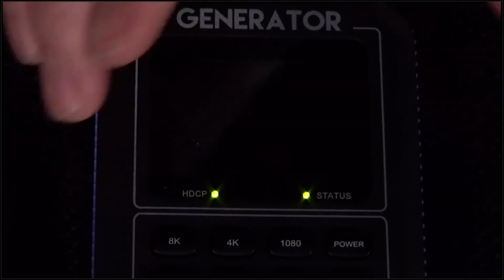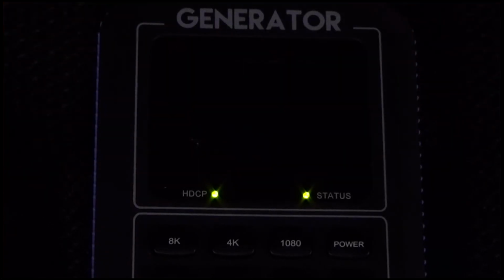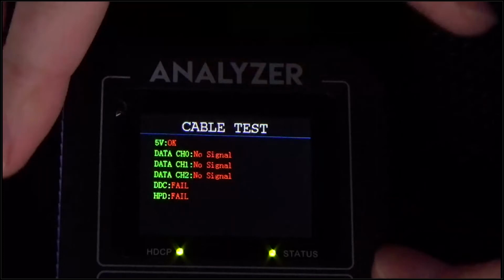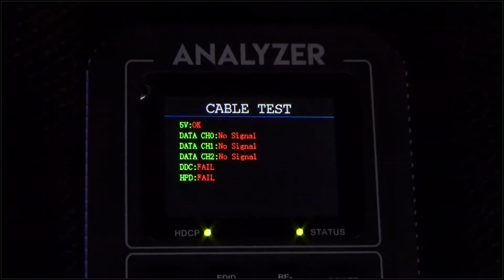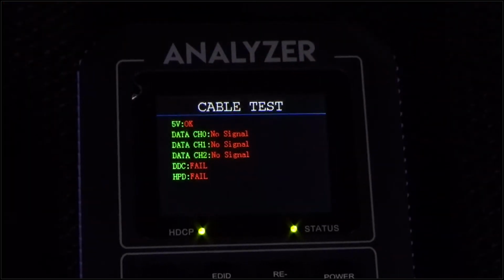Now on the analyzer end of things, I'll take an HDMI cable here, and you can see in the analyzer exactly what's going on with HDCP. So we're going to plug in to the generator, and then we're going to plug the other end into the analyzer. And I'll switch cameras so you can see the analyzer a little bit better. Now on the generator, I'm going to generate a signal with no HDCP. Again, we just want to see if there's a picture and sound getting through the system.